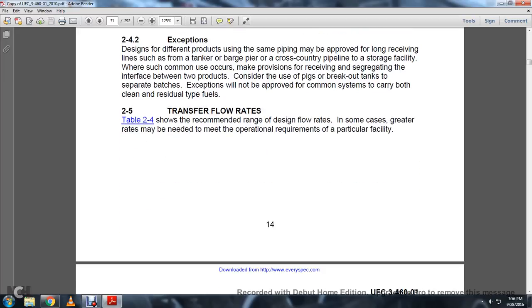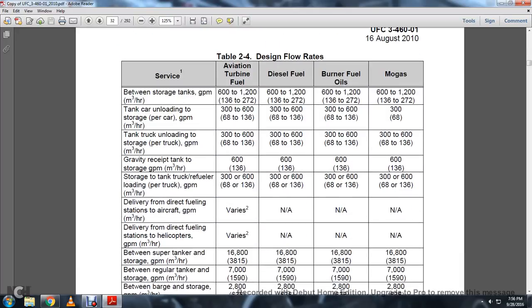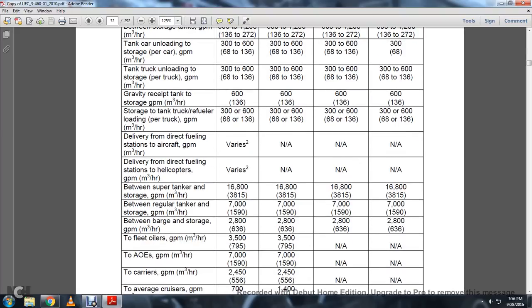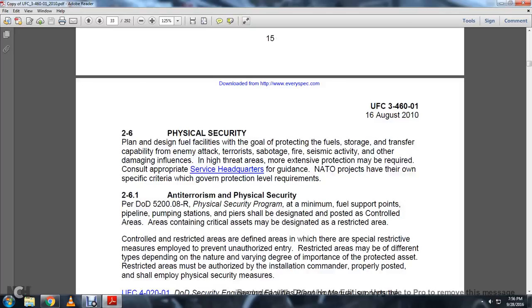2.5 transfer fuel flow rates. Table 2 shows the recommended range for the design flow rates. In some cases, greater rates may be needed to meet operational requirements of a particular facility. These are design flow rates for aviation turbine fuel designs, burner fuels, and oils and mogas under each storage, different storages.